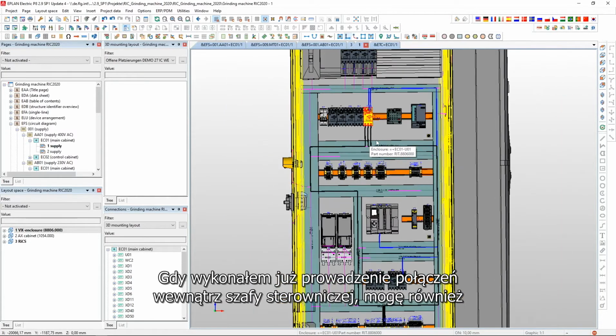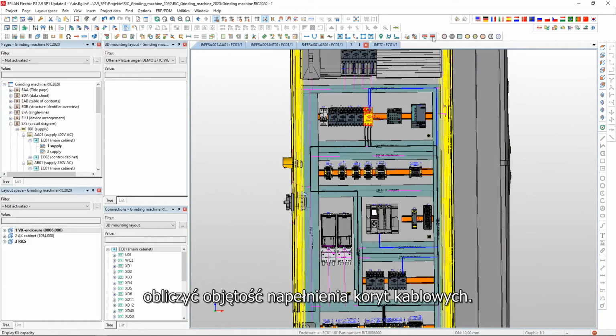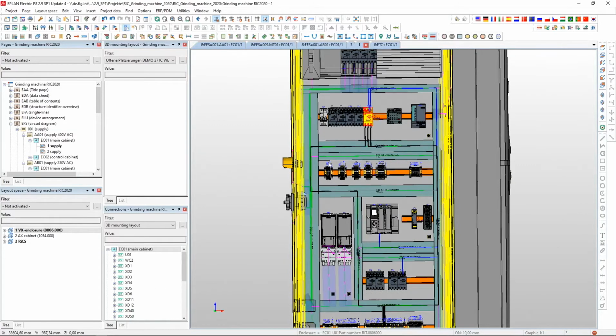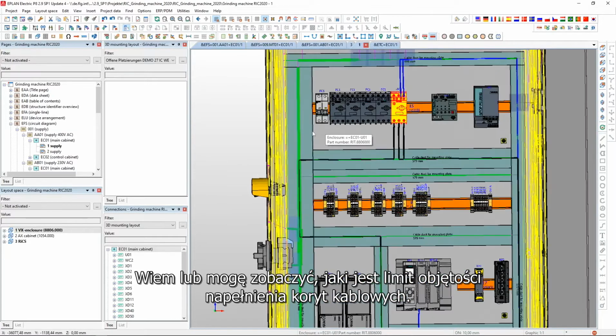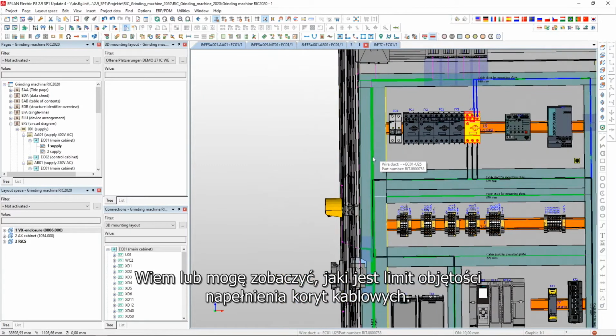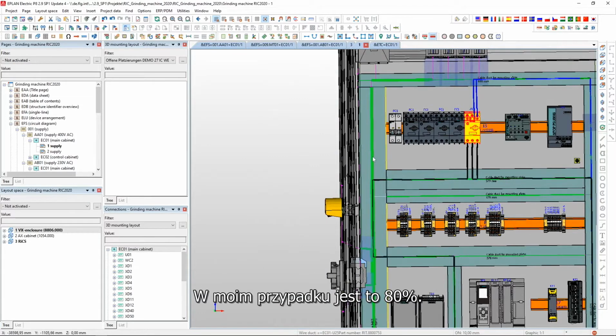If I've done all the routing inside my enclosure, I also have the possibility to calculate the fill capacity of my wire ducts. So I know, or I can see, that I've defined a limit of fill capacity for my wire ducts - for example, in my case, 80%.